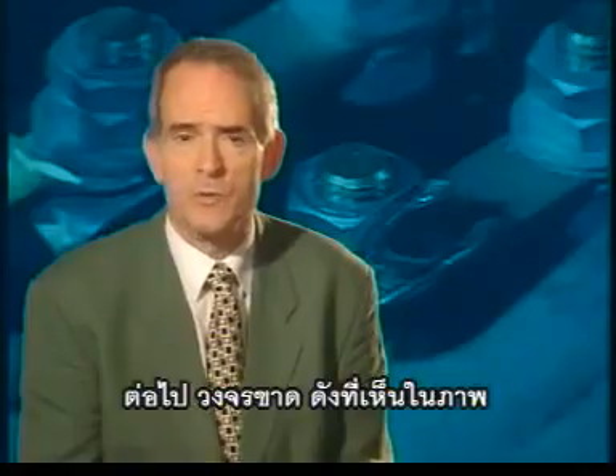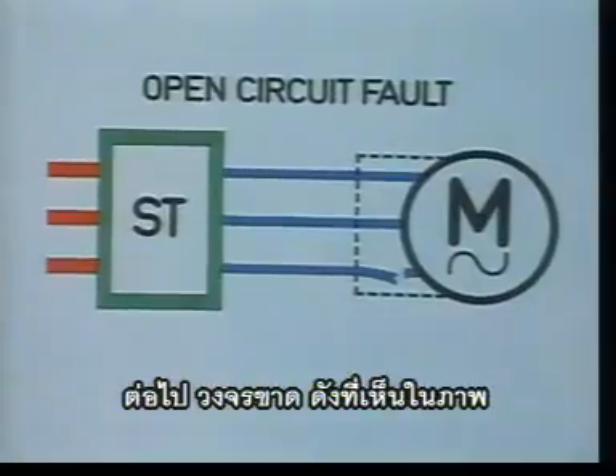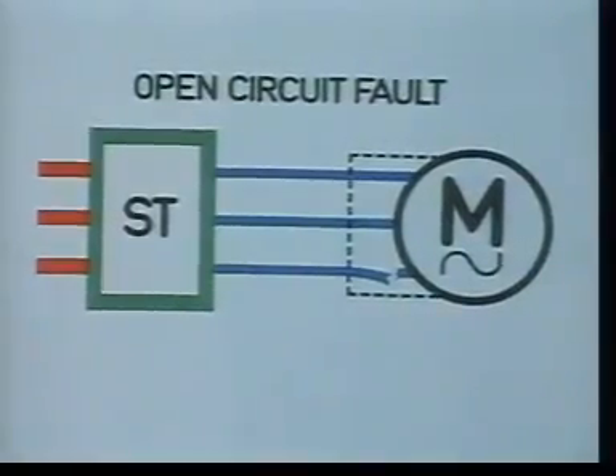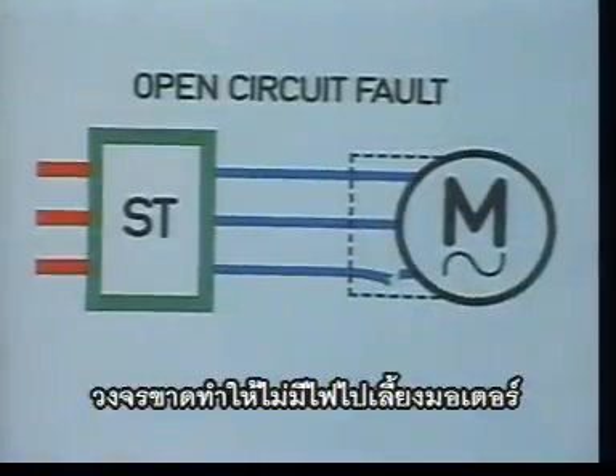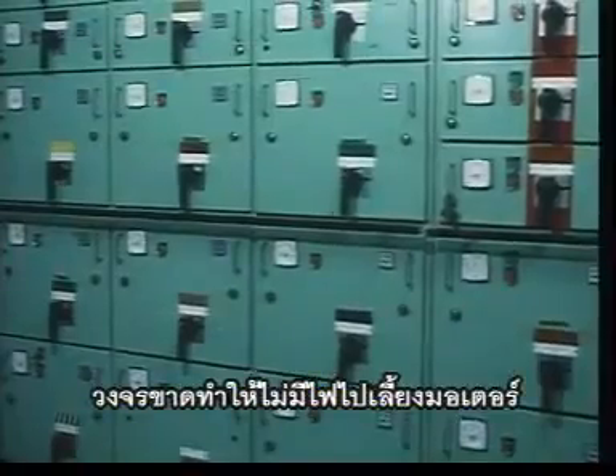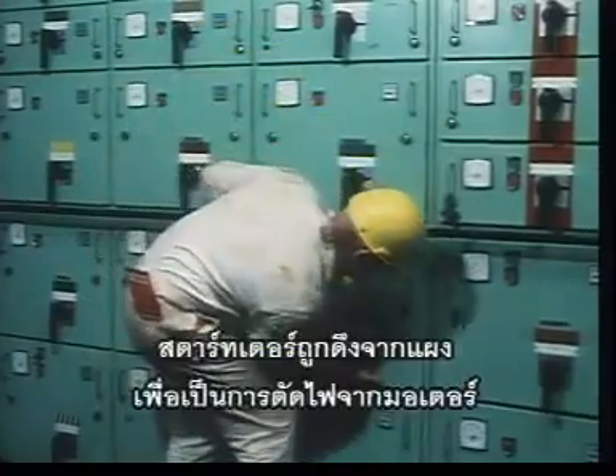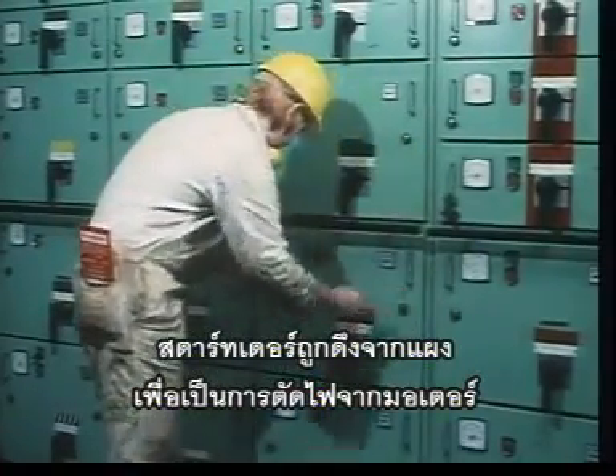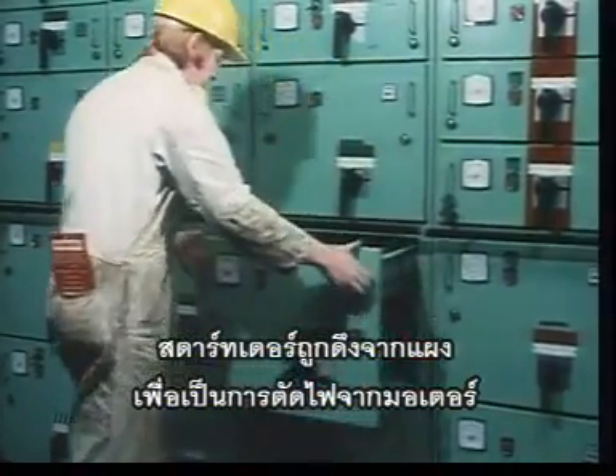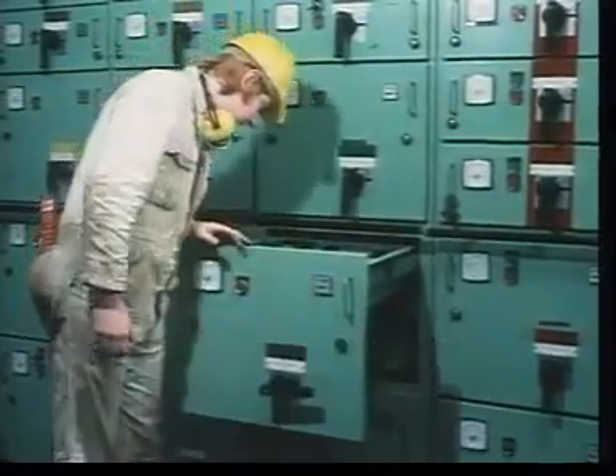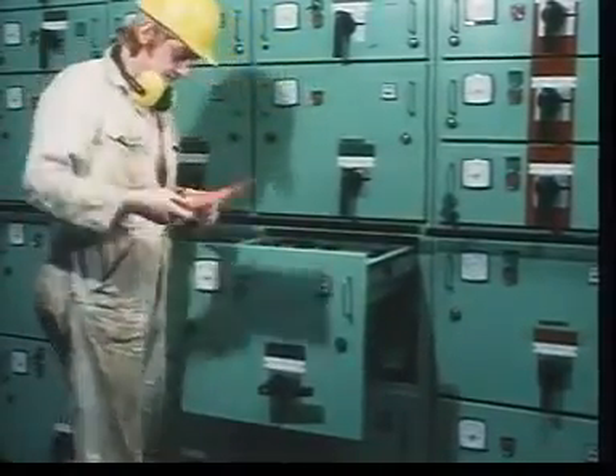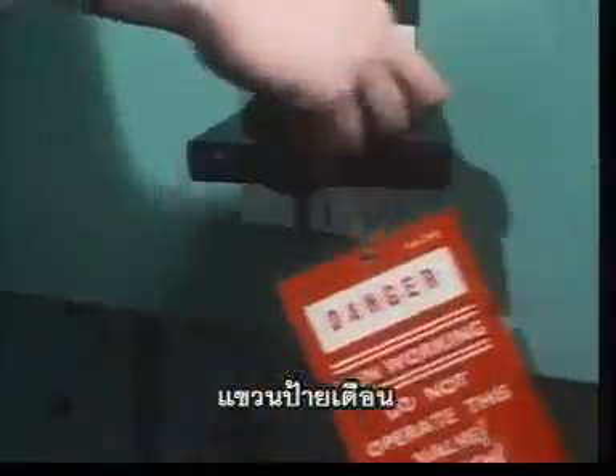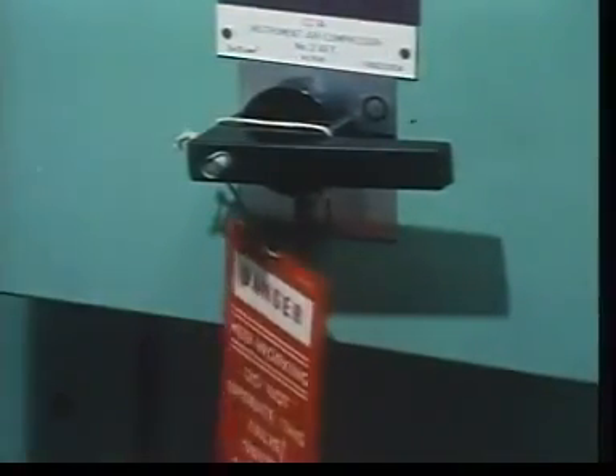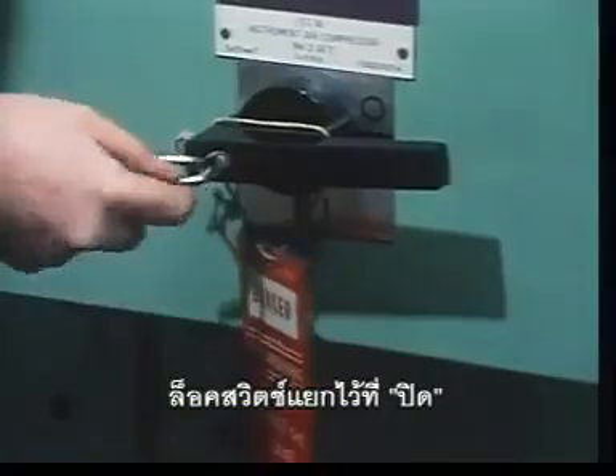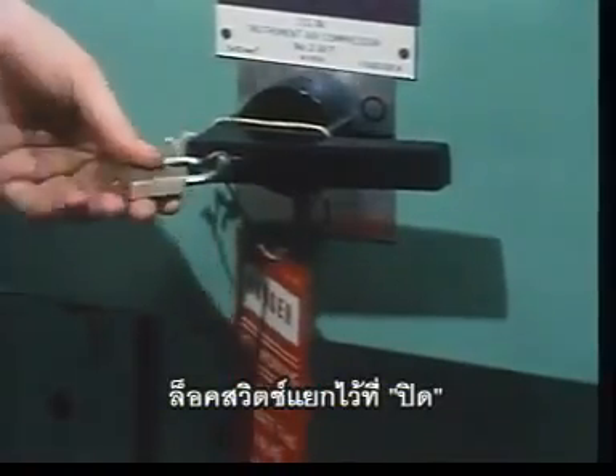Now we move on to open circuit faults, also illustrated here. An open circuit fault causes the loss of a service, in this case a motor. The starter is withdrawn from the board, effectively disconnecting the supply from the motor. A warning sign is posted and the isolator switch is locked in the off position.